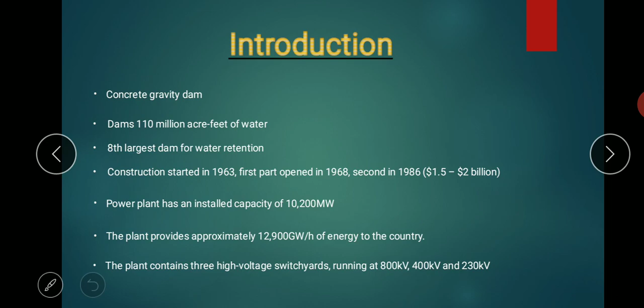The power plant has an installed capacity of 10,200 megawatt. The plant provides approximately 12,900 gigawatt hours of energy to the country. The plant contains three high voltage switchyards running at 800, 400 and 230 kV.